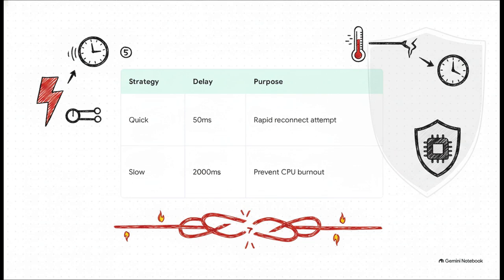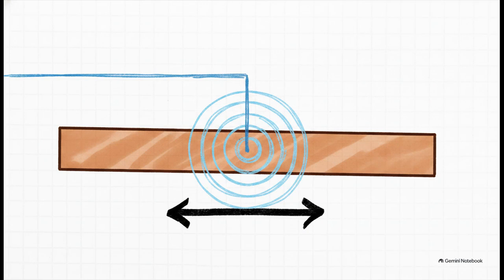But if it fails 5 times in a row because of a hard physical short, it's smart enough to switch to a 2000 millisecond slow recovery mode. This stops the transceivers in the CPU from just burning up by endlessly hammering a shorted circuit. And to physically block that electromagnetic coupling, the 3D design rules are brutal. They strictly ban parallel routing and demand a minimum 100mm air gap between the low-voltage comms and those massive high-voltage copper bus bars.